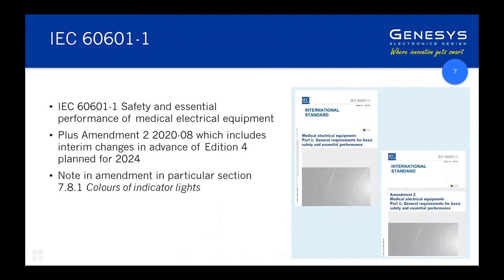The current version is Edition 3.1, but there's been an amendment that came out quite recently that some may not be aware of. There was going to be a major update in 2024, but the powers that be decided an amendment is required. It does have some quite substantial changes, particularly in the use of indicator lights, so I'd advise everyone to make sure they're across Amendment 2 while we wait for the new edition.